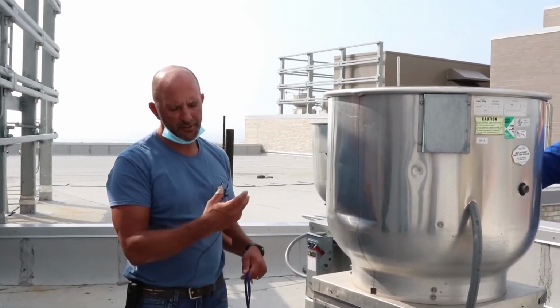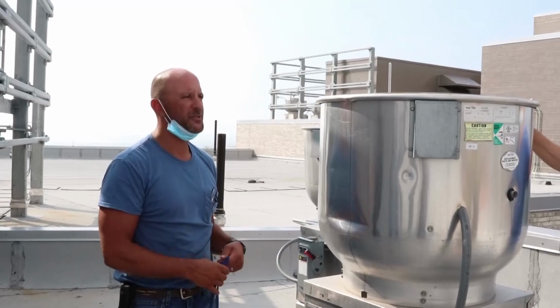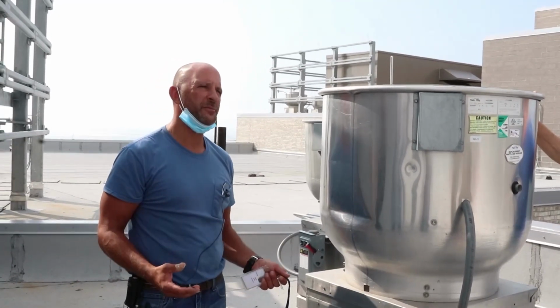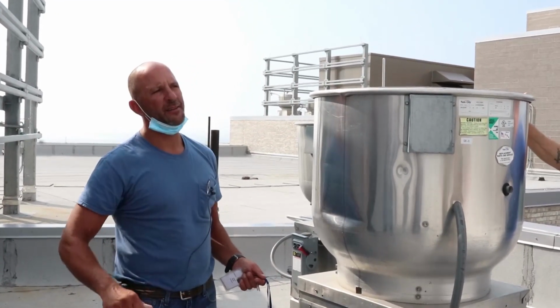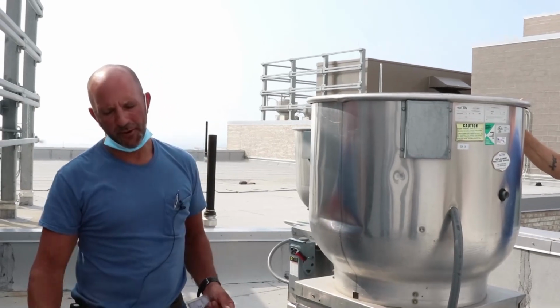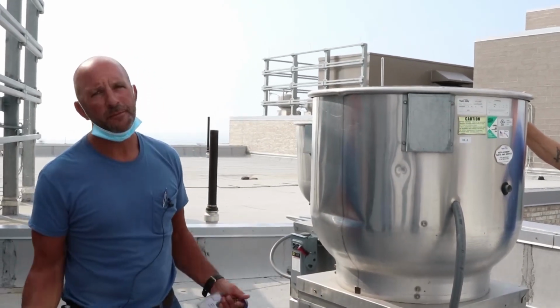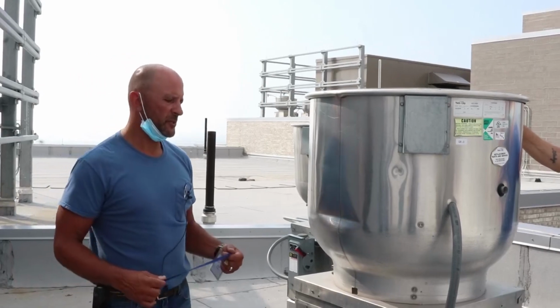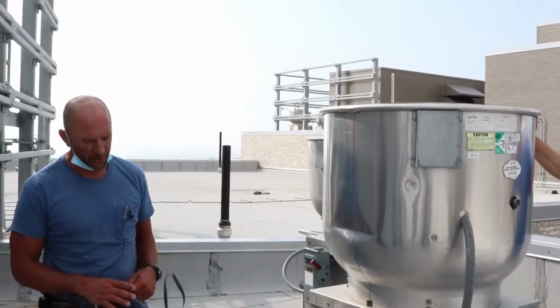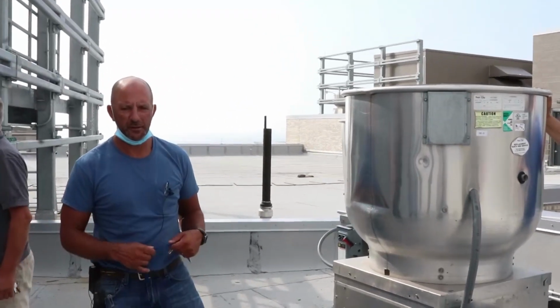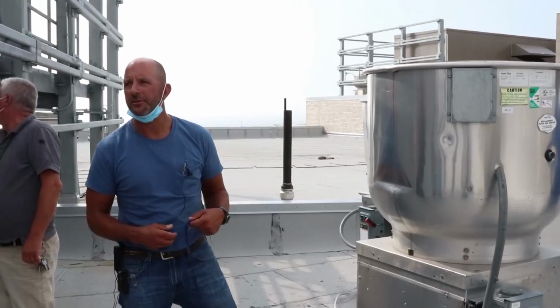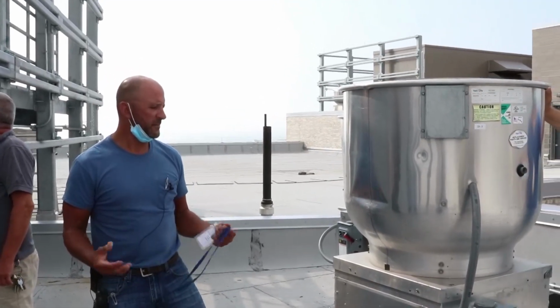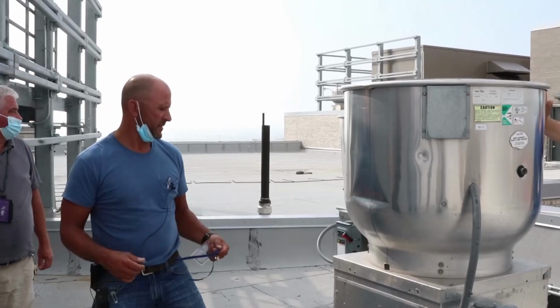When we do the training in the room for the as-builts, I'll make sure that we have the O&Ms, and we'll highlight the hours. Most bearings are greased on runtime, so we'd have to figure out the runtime hours. But with these running 24/7, I would say you've got to be checking them monthly at least, because you'd be checking the belts also.